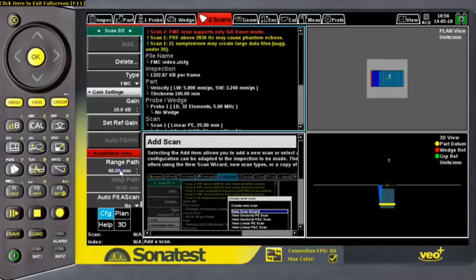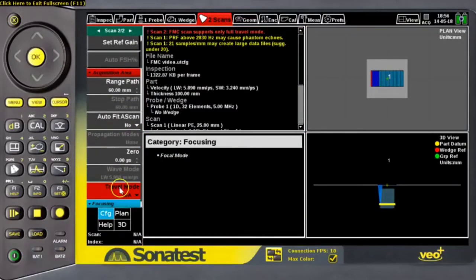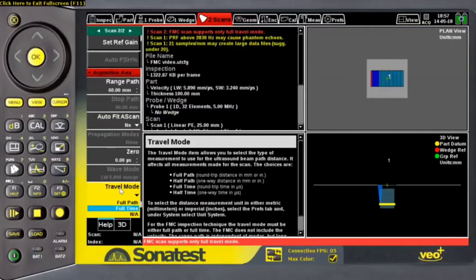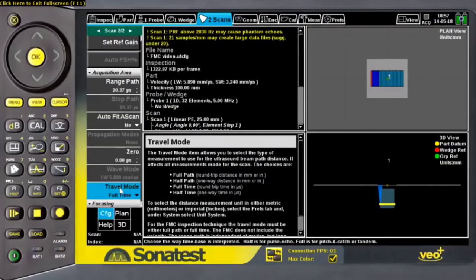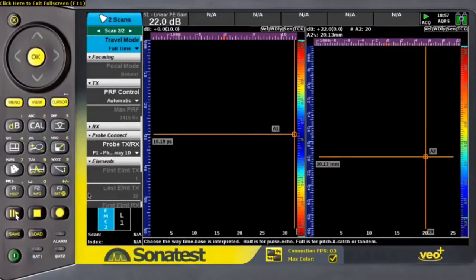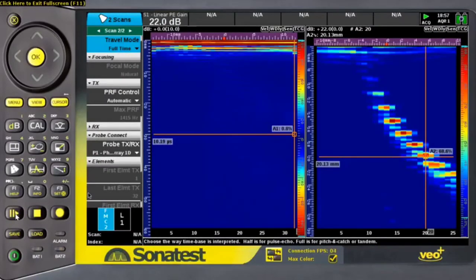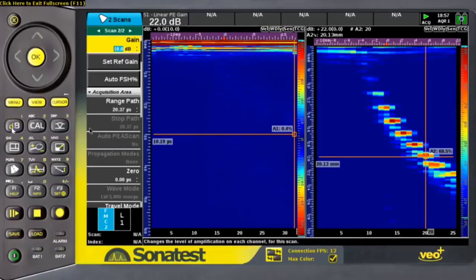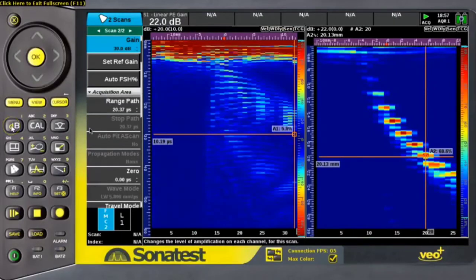Creating a new FMC scan on my instrument will give me the ability to record all the possible acoustic information under the phase array probe. Now, after setting my travel mode into full time, I can start the acquisition of my instrument. As we can see on the right, I have my linear scan and the defects, while on the left, this is my FMC scan that runs concurrently with my phase array scan.